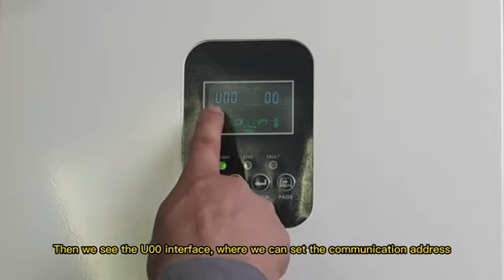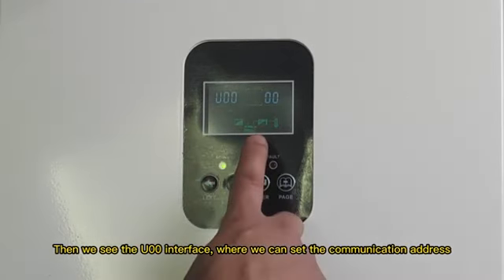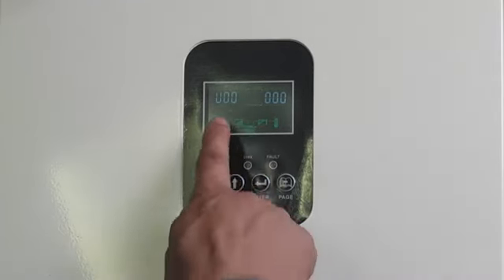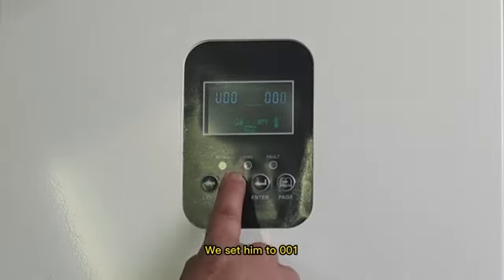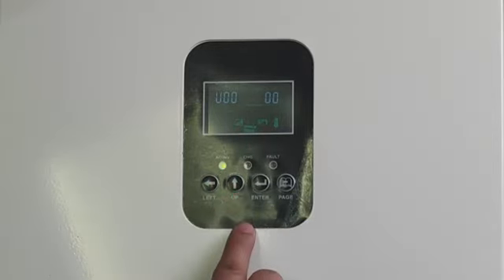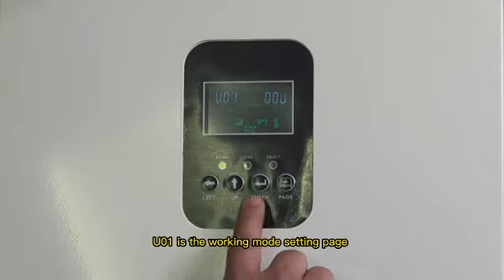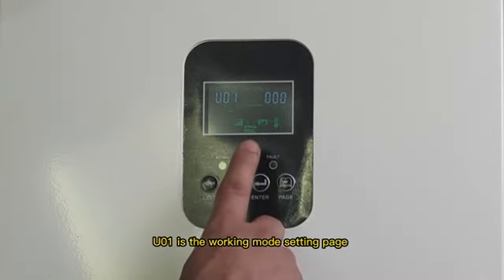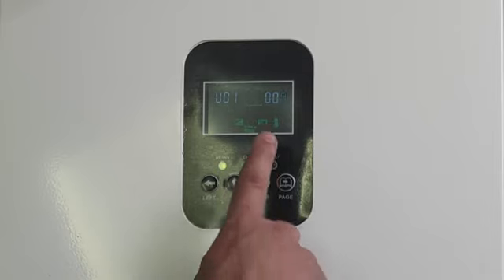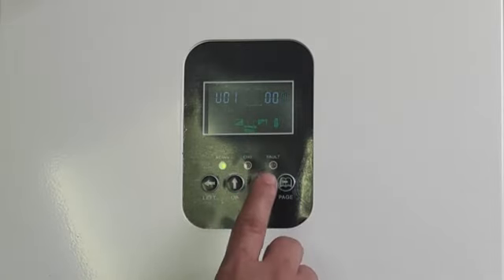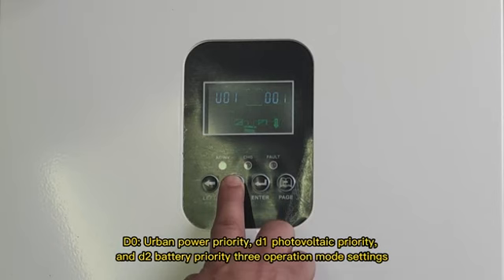Then we see the U00 interface where we can set the communication address. We set it to U1. U01 is the working mode setting page. D0, mains power priority; D1, photovoltaic priority; and D2, battery priority, three operation mode settings.